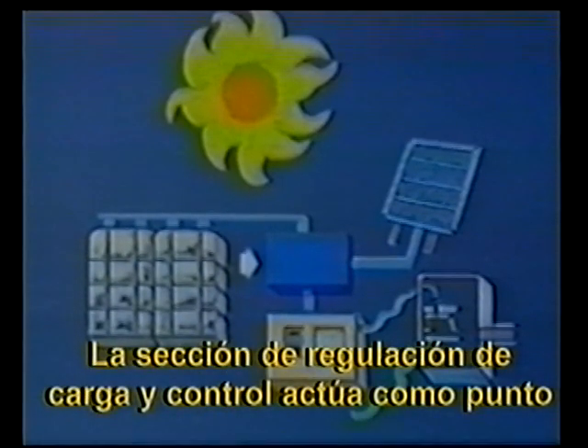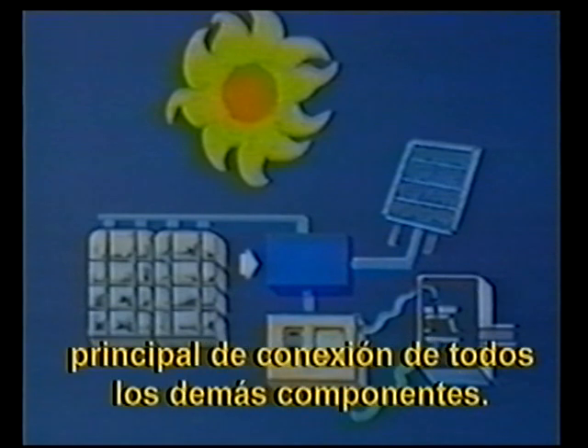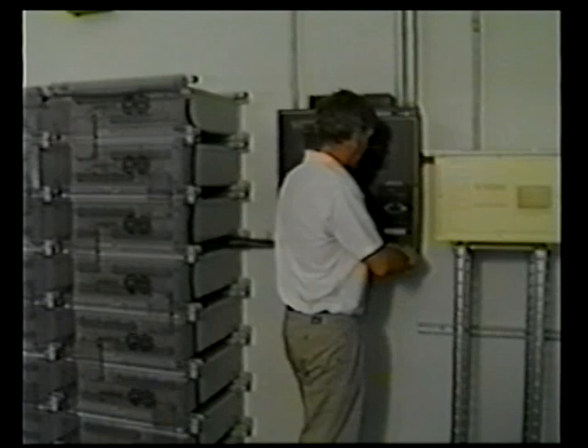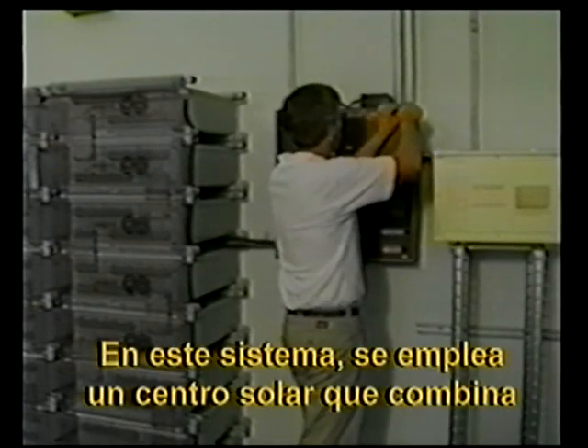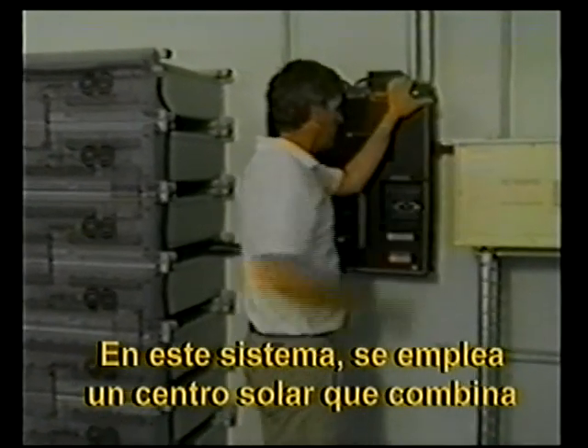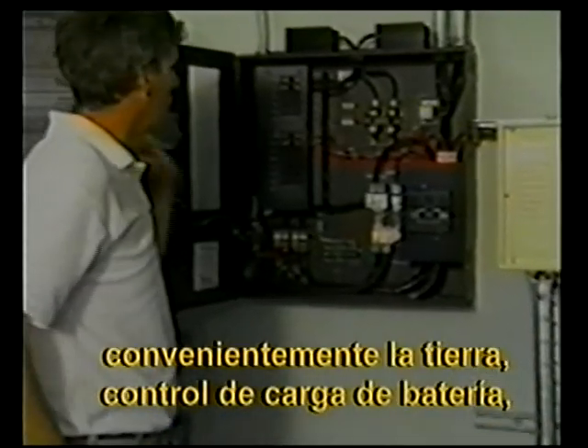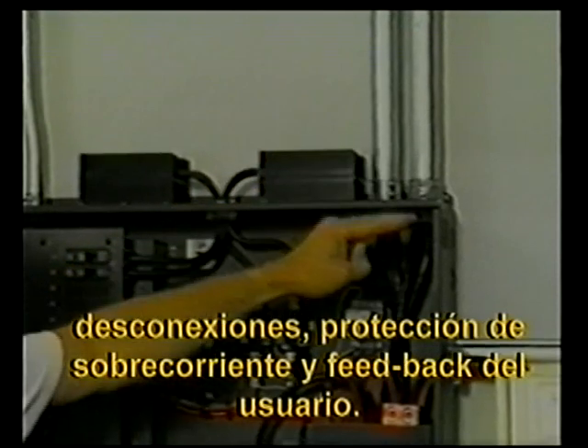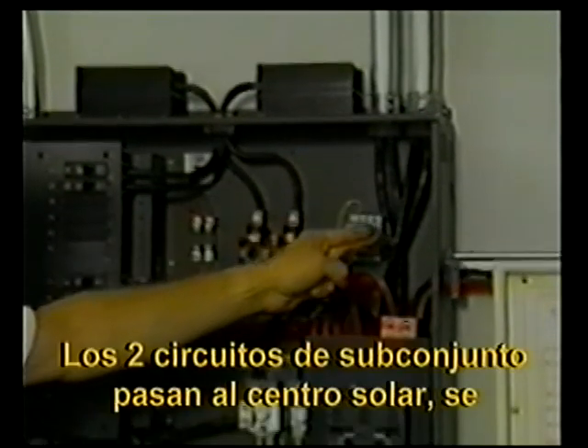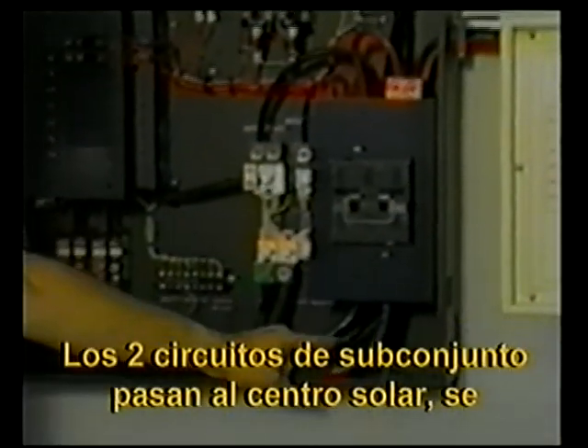The charge regulation and control section acts as a main connection point for all the other components. In this system, a solar center is used which conveniently combines grounding, battery charging control, disconnects, overcurrent protection, and user feedback. The 2 subarray circuits pass into the solar center, connect to their wiring blocks, and to separate DC-rated circuit breakers.